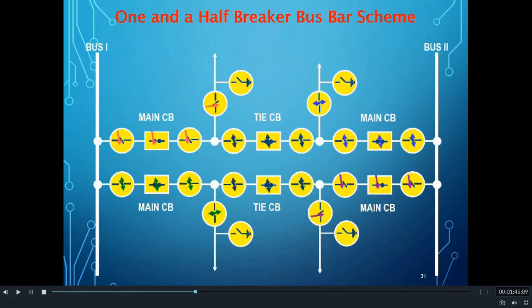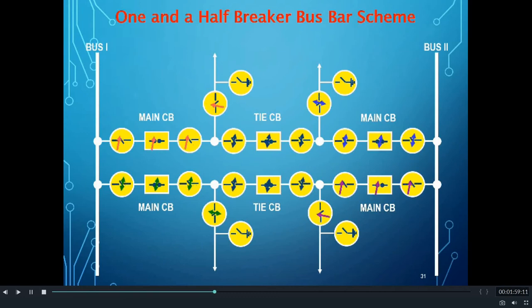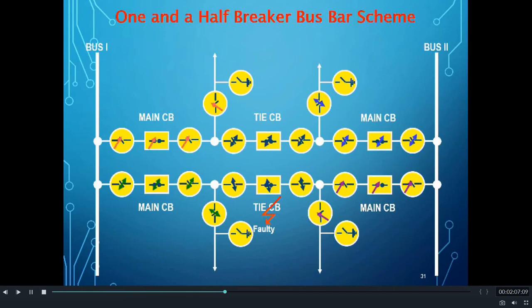All circuit breakers and isolators are shown and all are in service. From the figure you can see all feeders are connected to both buses through main and tie circuit breakers. Now we will see how this busbar scheme behaves when there is a fault — we have created a fault in the tie CB.